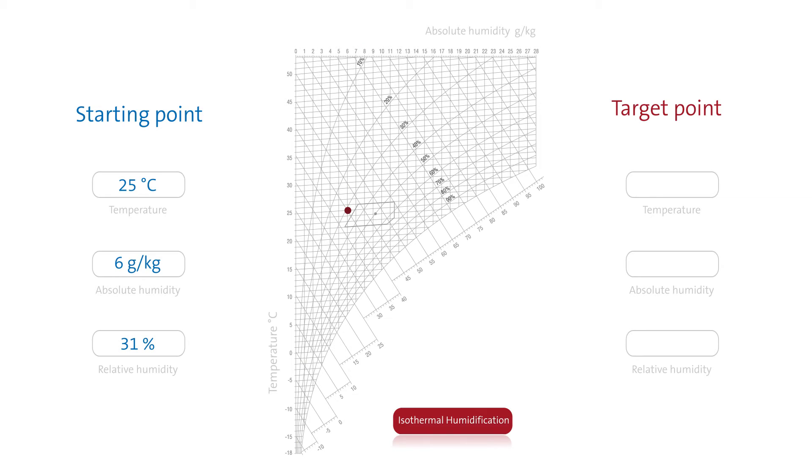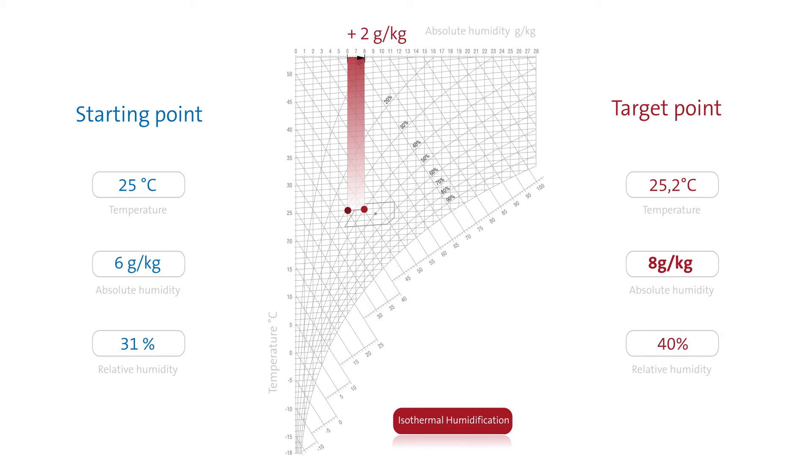If the air at these conditions is humidified by 2 grams of water per kilogram using a steam humidifier, we reach a target point of 8 grams of water per kilogram of air and 40% relative humidity at almost constant temperatures.